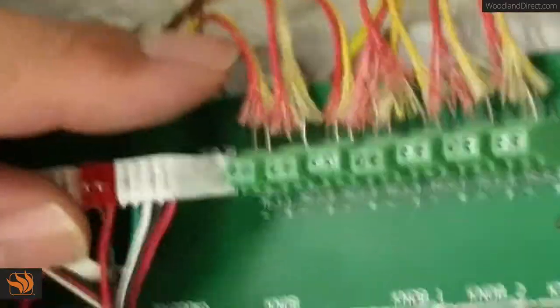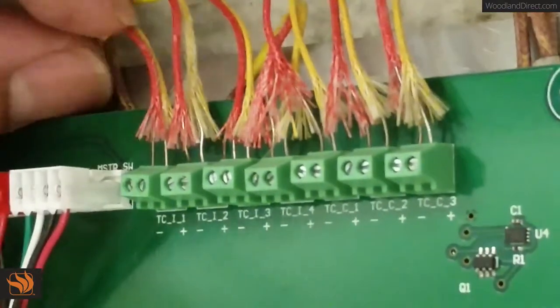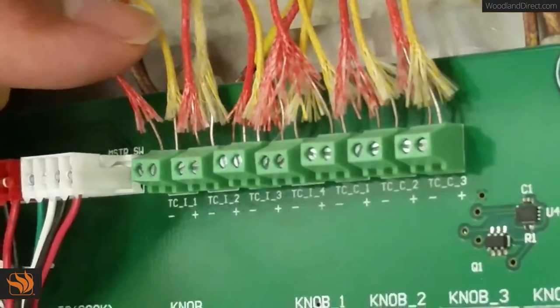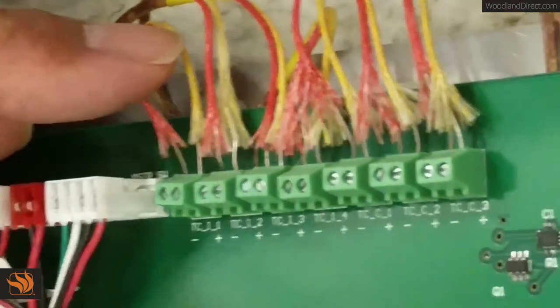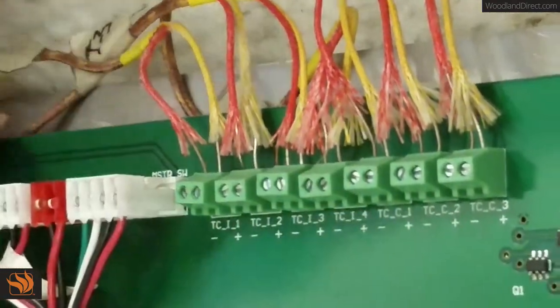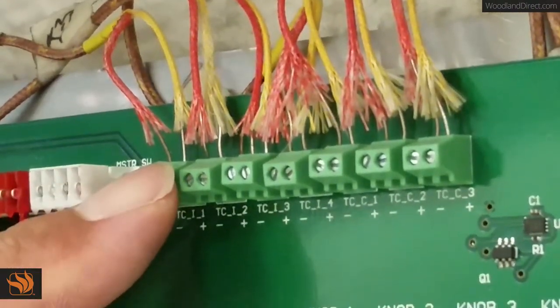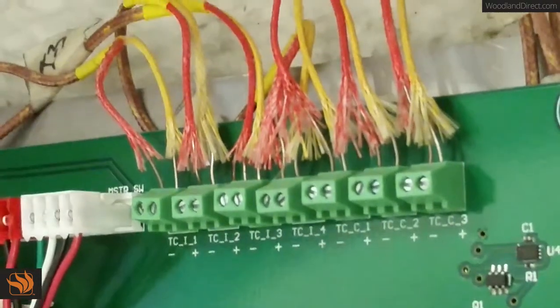If you look at the wire, you have a red and a yellow wire. The red wire will always be negative, the yellow wire will always be positive. At a glance you can check to see that you have the proper polarity across all of the connections. Both the igniter thermocouples and the cook thermocouples should be wired the same way.